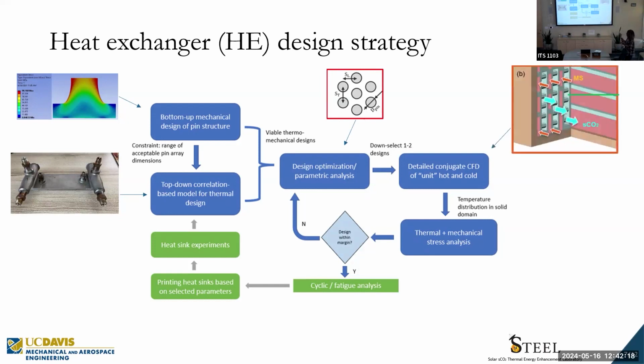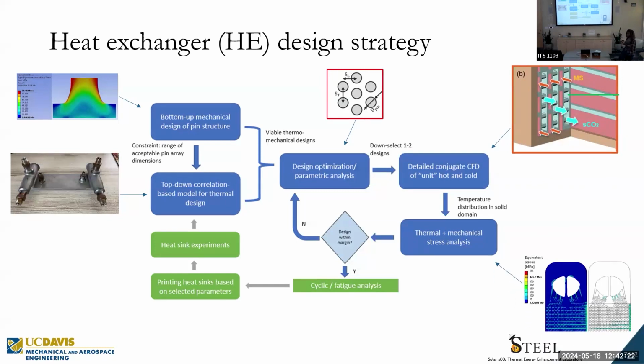After selecting this best case scenario, we ran CFD and FEA simulations. In the CFD, we want to look at thermal performance and also obtain the temperature distribution within the heat exchanger so we can assess the thermal stresses. These thermal stresses are added to the mechanical load, the pressures in the unit, to get a combined thermal-mechanical stress for the heat exchanger.